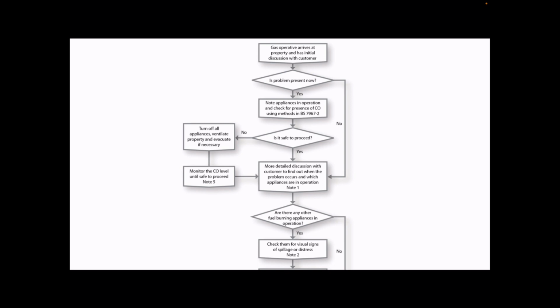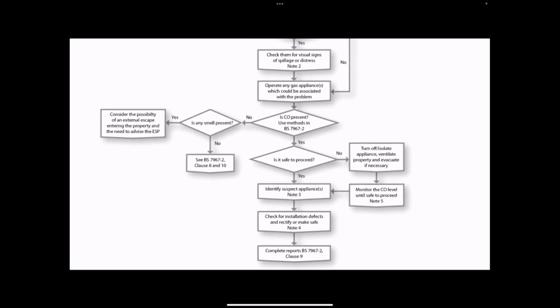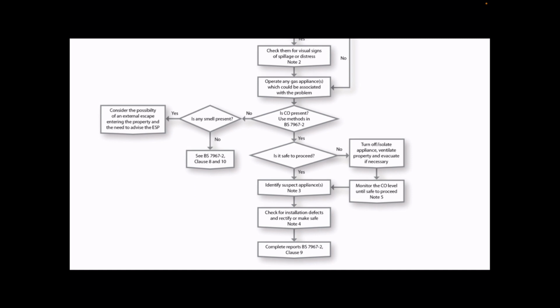And then you move down and the next box says, is the problem present now? Well, if it is, you go straight down to where it says note appliance in operation and check for the presence of carbon monoxide using the approved methods. If the problem's not present, then you follow the other route, which takes you to a box which says more detailed discussion with the customer to find out when the problem occurs and which appliances are in operation when it does occur. So you can see this is simply a flow chart. You ask the question. If the answer is yes, you follow one arrow. If the answer is no, you follow the other arrow. Very simple. In your assessment, if you're asked to do this, or if in your exam there's a question about this, just follow the flow chart. It will give you the answer.